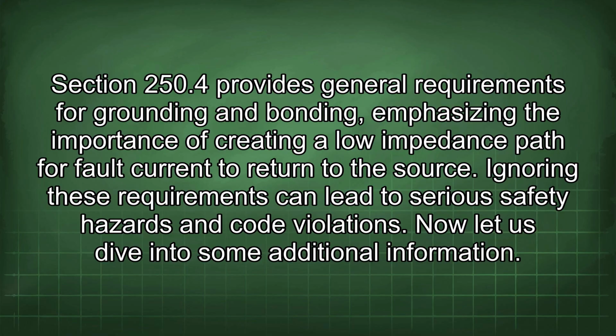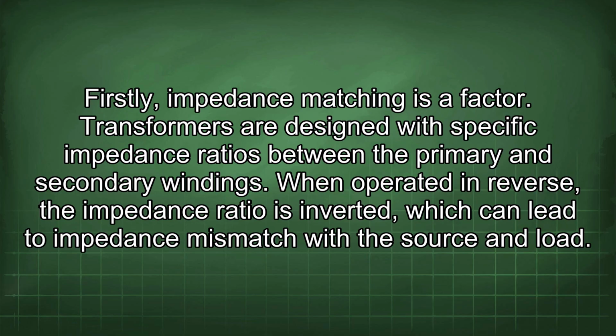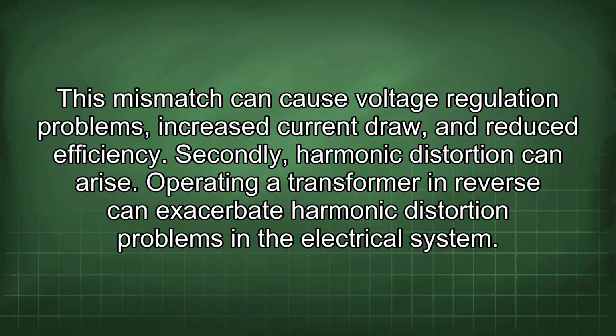Now let us dive into some additional information. Firstly, impedance matching is a factor. Transformers are designed with specific impedance ratios between the primary and secondary windings. When operated in reverse, the impedance ratio is inverted, which can lead to impedance mismatch with the source and load. This mismatch can cause voltage regulation problems, increased current draw, and reduced efficiency.